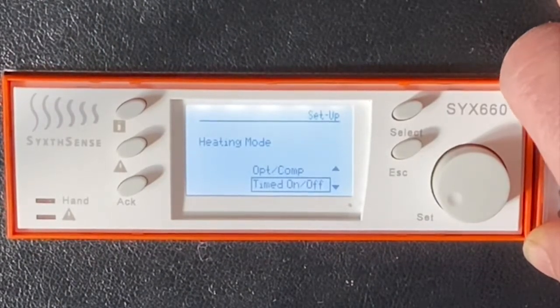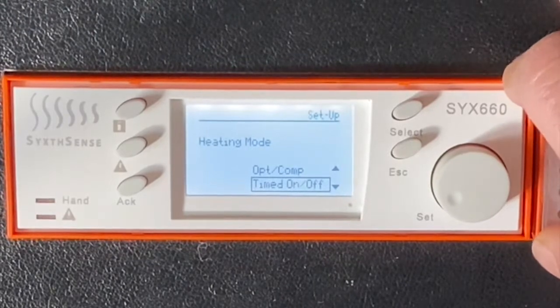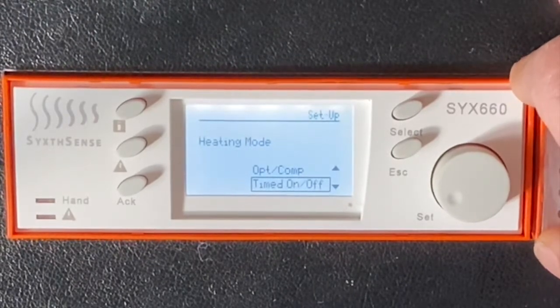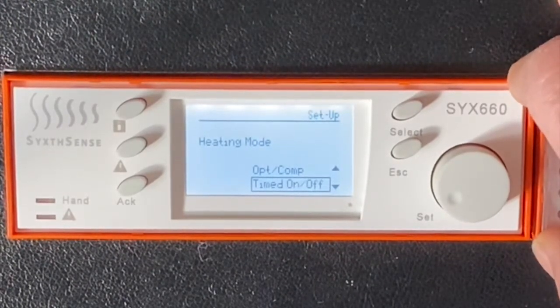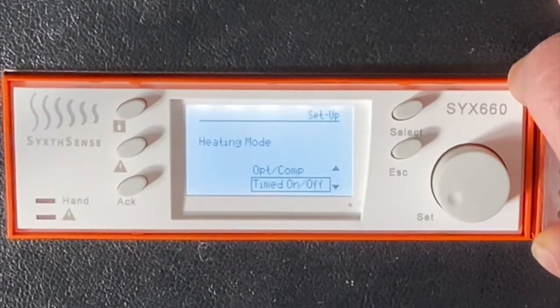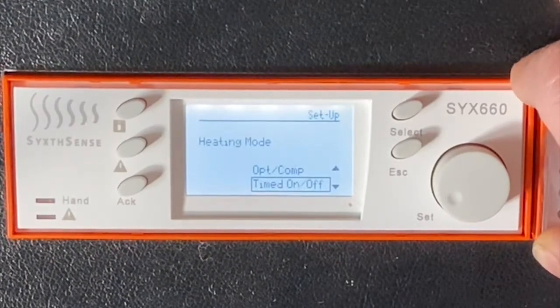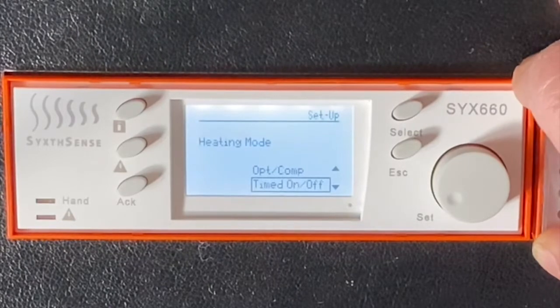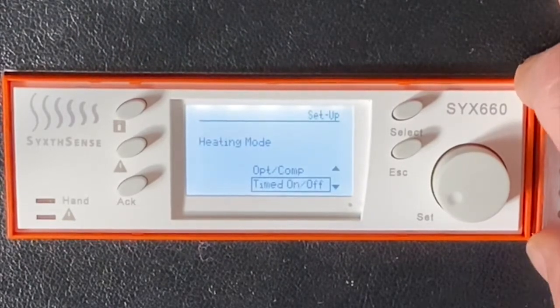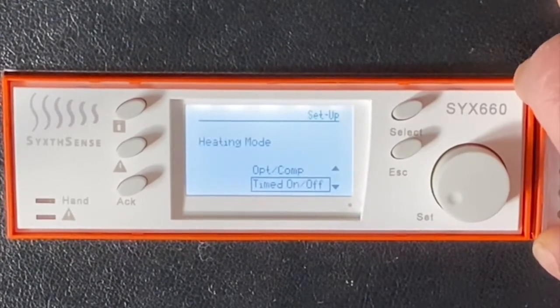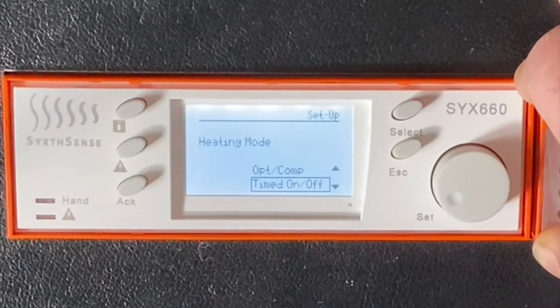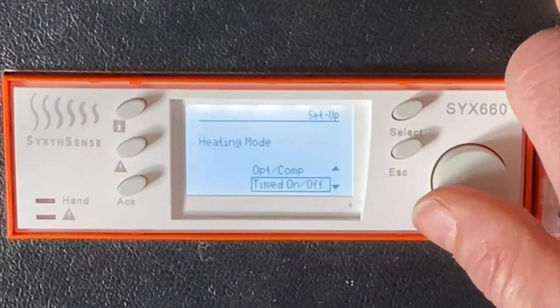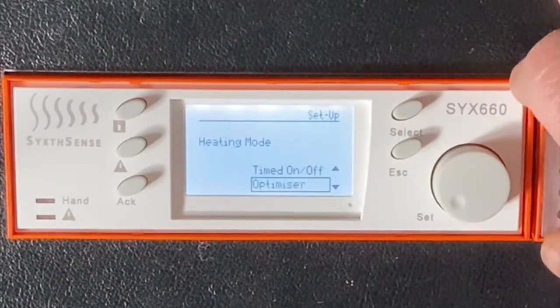Some residential applications get a little bit disturbed by heating plants starting up at unexpected times of the day. Because they have such fast warm-up rates, sometimes the optimizer could be a little bit disconcerting for people who don't expect the heating to be running when they haven't programmed it. So timed on off is a feature for that.